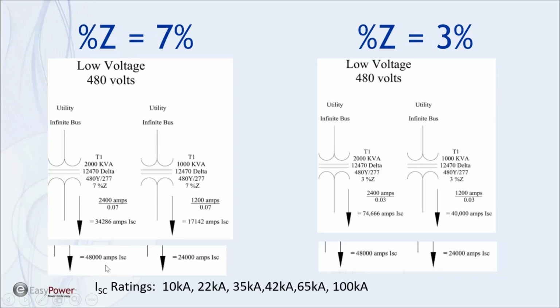So you can see here it's gone from 48,000 amps at 7% impedance down to 34.2 kA on the 2,000 kVA at 480 volt. On the 1,000 kVA at 480 volt, it goes from 24,000 down to 17,000. Now I stuck with the 480, but I looked at decreasing the percent impedance, and because I went up by 2% above 5% in this example, I went down by 2% to 3%. So you can see what happens here. It goes from 48,000 to 75,000, and 24,000 up to 40,000. So that's the impact that the percent impedance can have on available fault current.